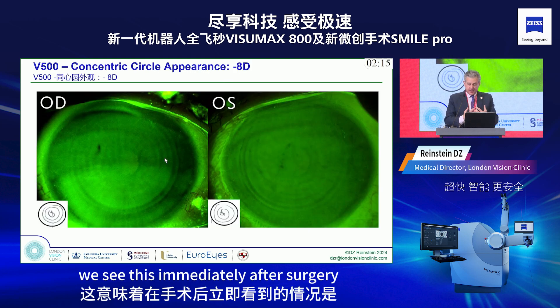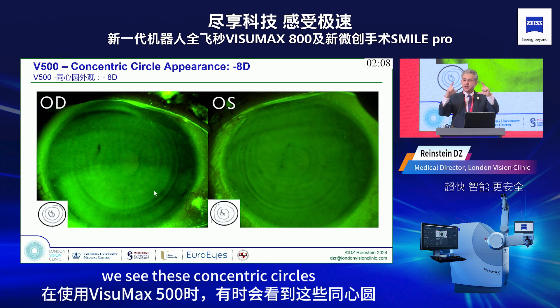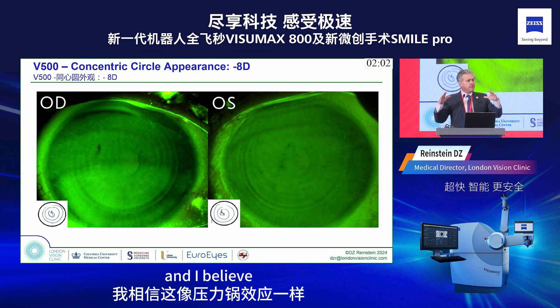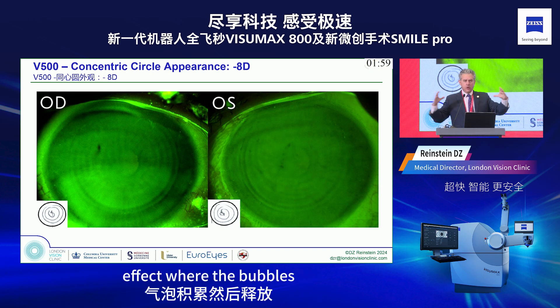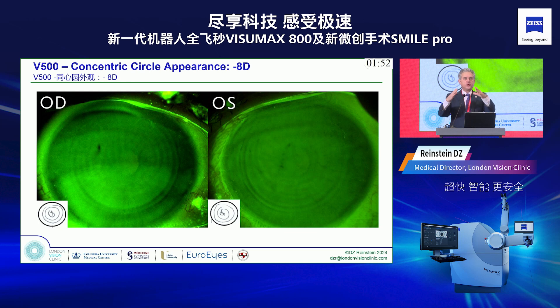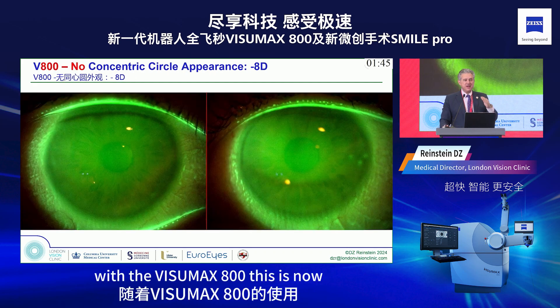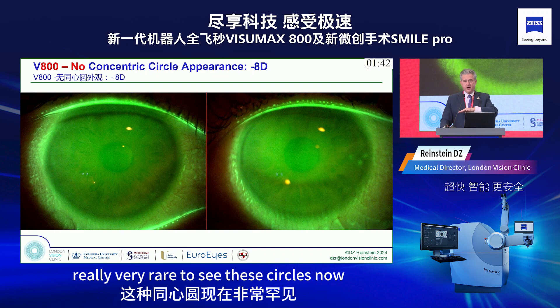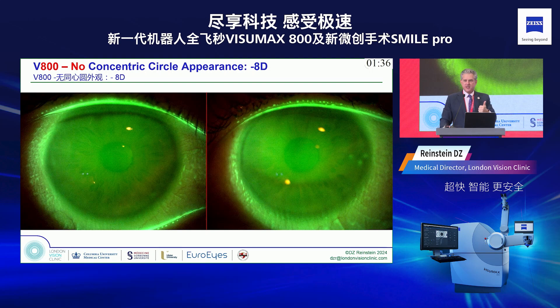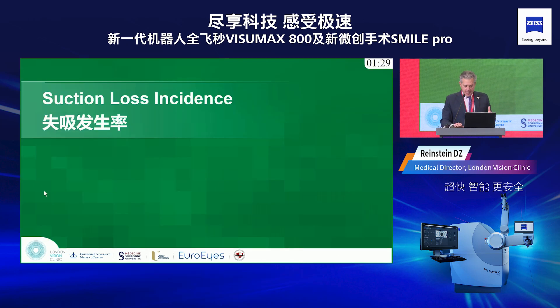This is seen immediately after surgery: with the VisuMax 500, we sometimes see concentric circles when we apply fluorescein. After much investigation, I believe it's almost a pressure-cooker effect where bubbles accumulate and then release as the laser line progresses. With the VisuMax 800, these circles are now very rare, and that means day-one visions are better — the concentric circles would otherwise improve over time only through epithelial remodeling.